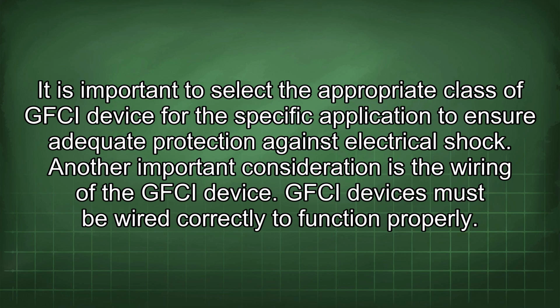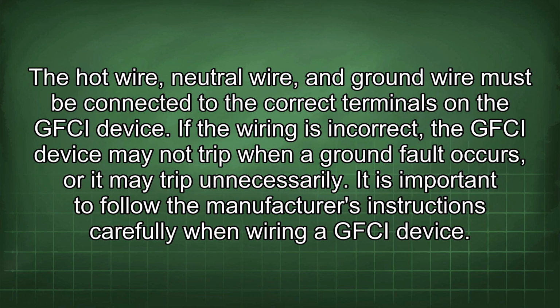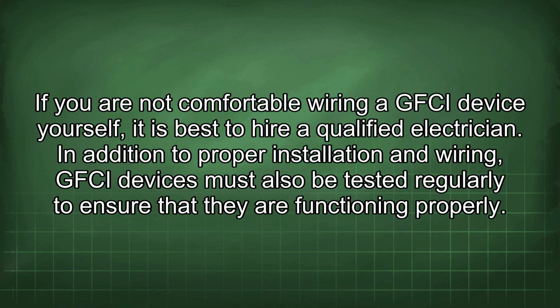GFCI devices must be wired correctly to function properly. The hot wire, neutral wire, and ground wire must be connected to the correct terminals on the GFCI device. If the wiring is incorrect, the GFCI device may not trip when a ground fault occurs, or it may trip unnecessarily. It is important to follow the manufacturer's instructions carefully when wiring a GFCI device. If you are not comfortable wiring a GFCI device yourself, it is best to hire a qualified electrician.